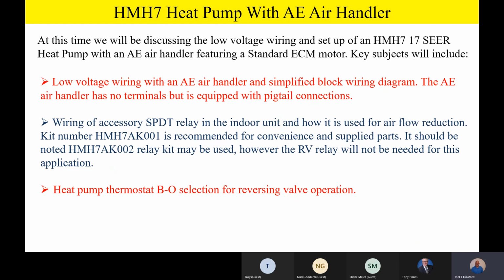We're going to get into the low voltage wiring on that AE air handler, and we're going to be looking at a simplified block wiring diagram. Now, please remember the AE air handler has no physical hard screw-on terminals, but is equipped with pigtail connections. Now, in my block diagram, I show our thermostat wires landing on a terminal. Just please remember they're pigtails, but for ease of putting things together in the PowerPoint, we're just showing terminals, even though they're actually pigtails. In addition, we're going to talk about wiring of the accessory single pole double throw relay in the indoor unit and how it's going to be used for airflow reduction.